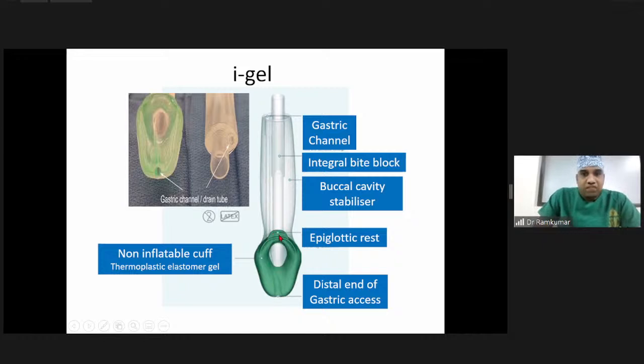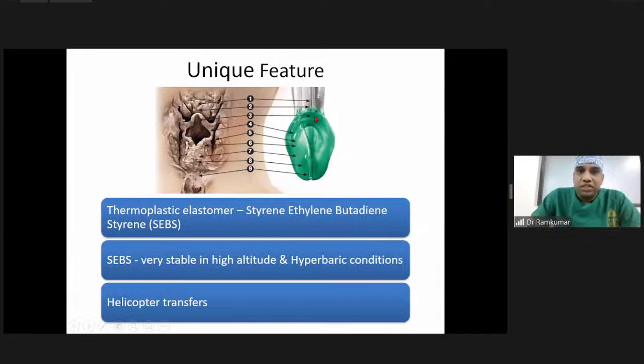And there is a small projection in the cuff called the epiglottic rest, which prevents the epiglottis from obstructing your ventilation. And as I said, this is the tip of the device where the drain tube, the nasogastric tube, comes through, and the entrance is at the upper end on the right side of the ventilating lumen. The important feature is this mask, this cuff, which is made up of a thermoplastic elastomer. The chemical name is styrene ethylene butadiene styrene. It is not uniform in shape. It has some elevations, depressions and notches, which are exactly the mirror image of the periglottic structures. So it fits very well as it is inserted and adapts with body temperature. It fits the periglottic structures very well, so it gives very good ventilation and a very high oropharyngeal leak pressure.